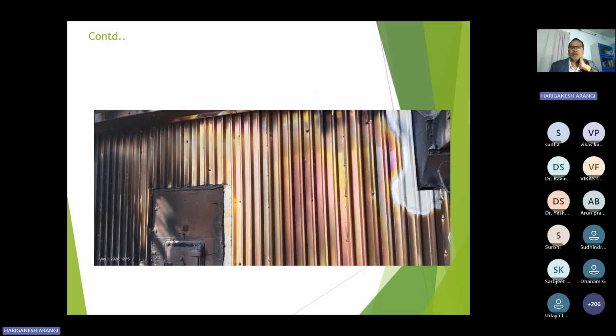You can see how the radiation affects because of improper insulation inside the boiler. You can see the outside insulation cover, that insulation cladding sheet, how the color has changed. It became pink and a reddish color. This is because of improper insulation, and this is a huge loss to boiler efficiency.